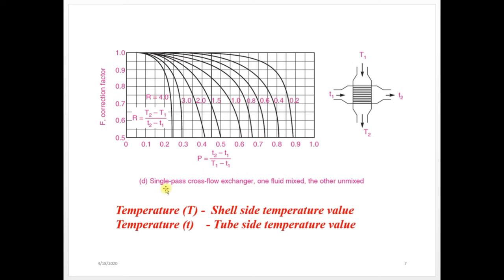In the fourth graph, it refers to single pass cross flow heat exchanger with one fluid mixed and other fluid unmixed. It is a cross flow type heat exchanger where one fluid is mixed and the other fluid is unmixed. By referring P and R values, you can find out the correction factor F value. Please remember: capital T refers to shell side temperature and small t refers to tube side temperature, because these two temperatures are required to find out P and R value, and based on P and R value you will get correction factor F.